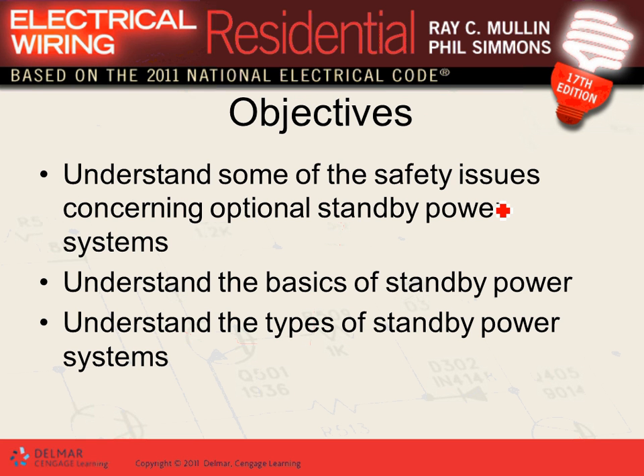Okay. The first thing we need to do, when you own and operate a generator, is be aware that there are other safety issues. Safety concern, optional standby power system: you're running a diesel engine generator or natural gas engine generator. There are fumes to pay attention to, and there's fire hazard. There's more hazard than just bringing power lines into your building, so you have to be aware of that.